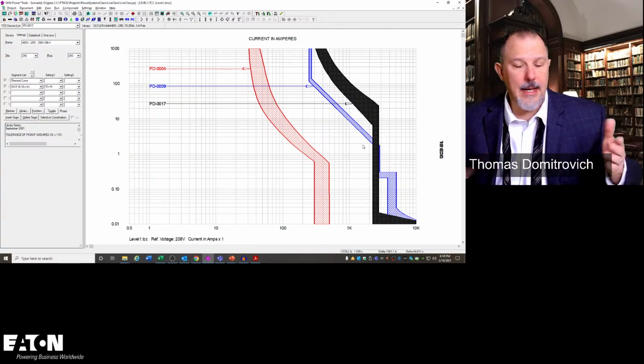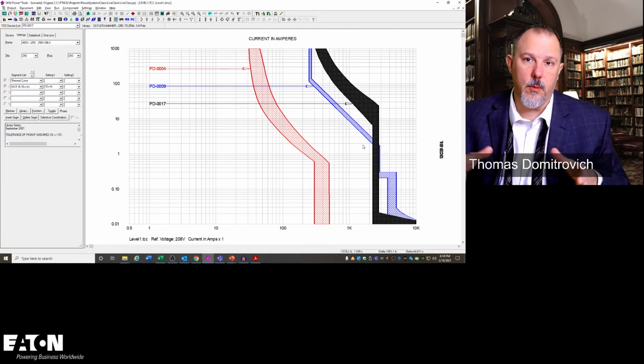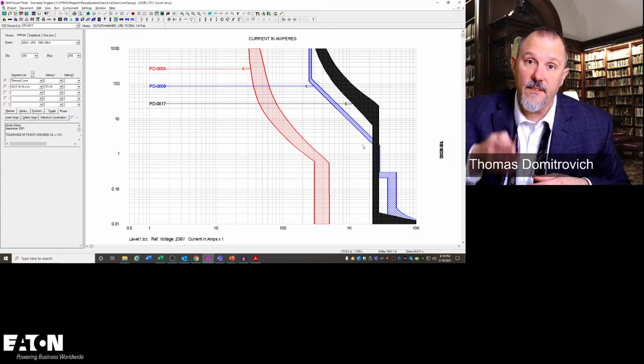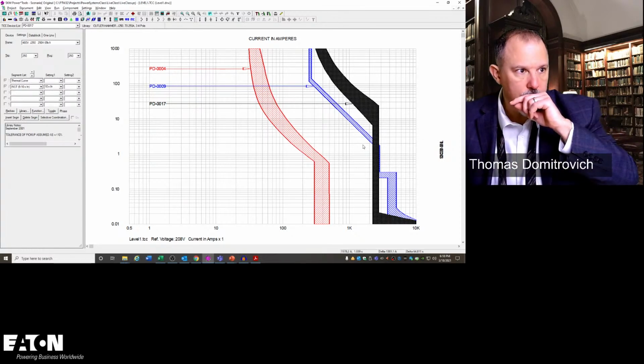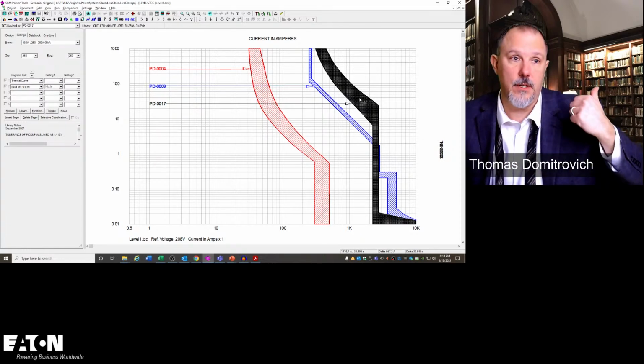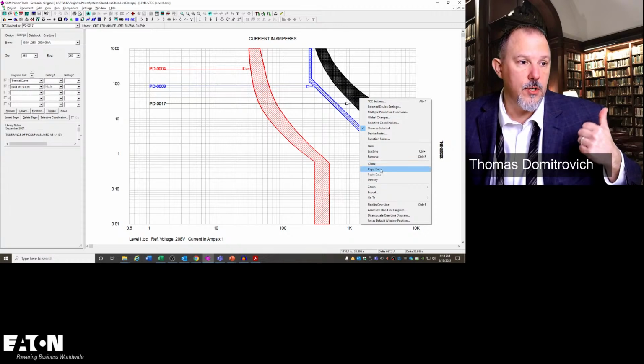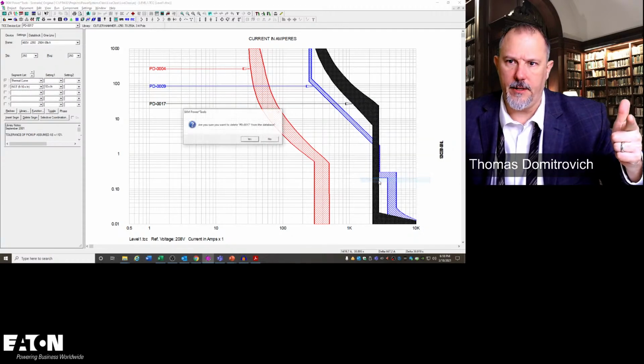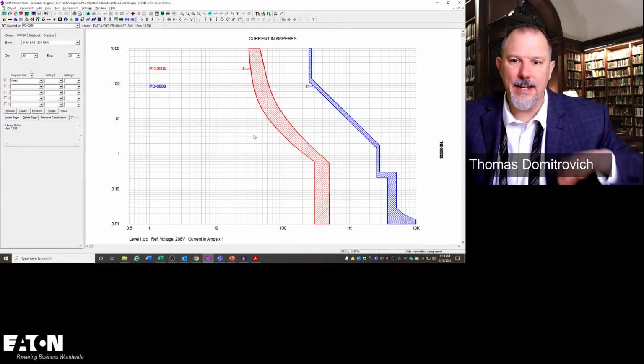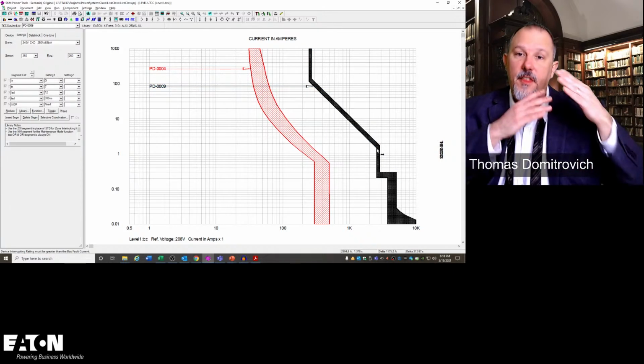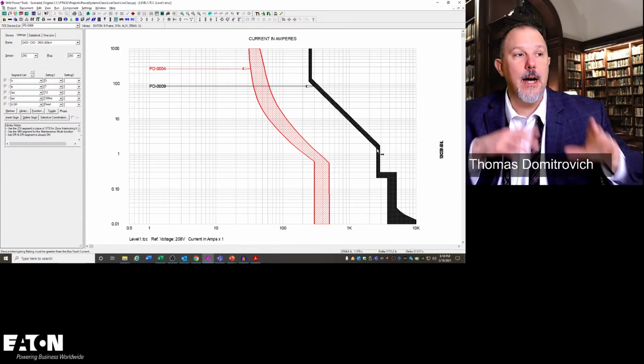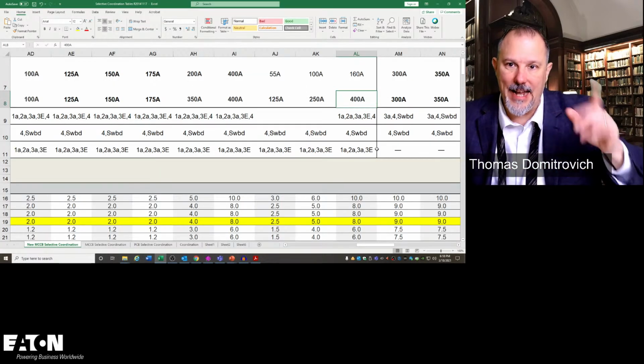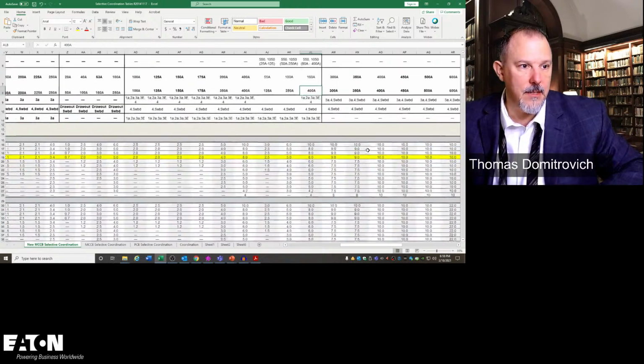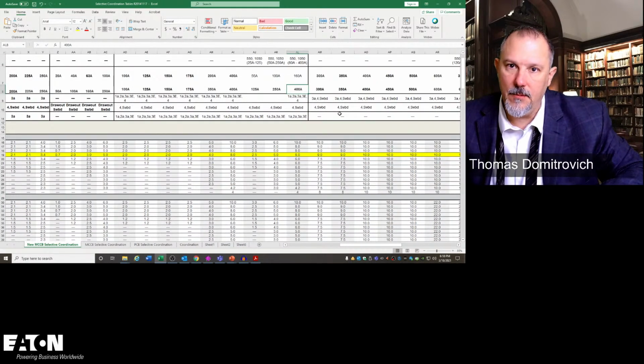So in any case, some level of coordination is good, and I think you always have to consider fault current. Now, so we know this guy is out from a selective coordination, so I'm going to destroy it. I hit destroy and it is gone from the system. So that is why I picked this breaker at 250 electronic trip unit. I based it upon the fault current that was at that point in the system, and I used the tables.